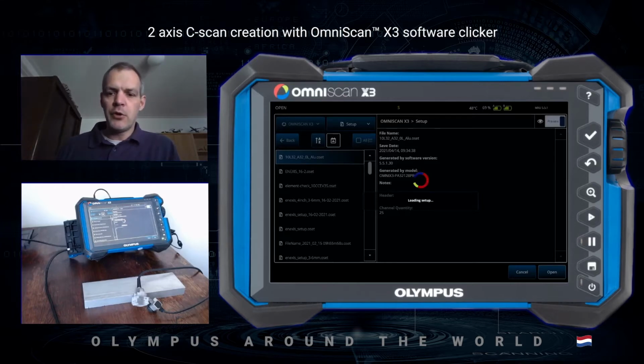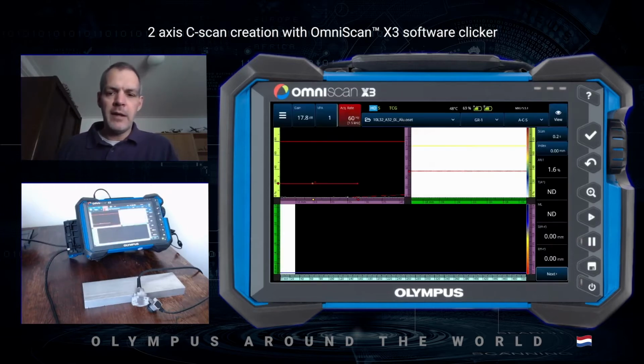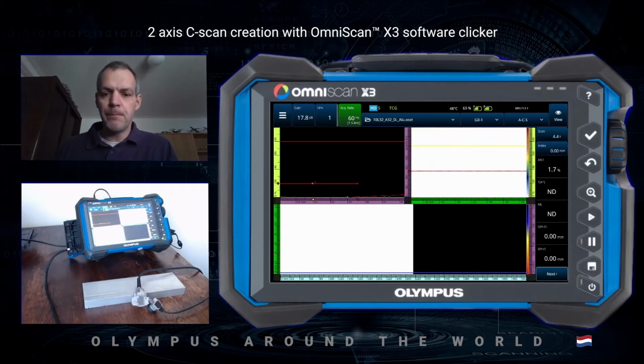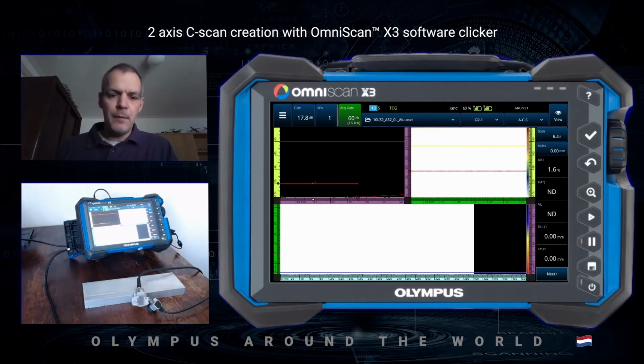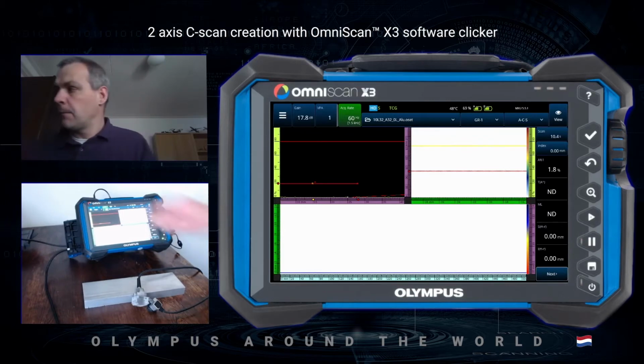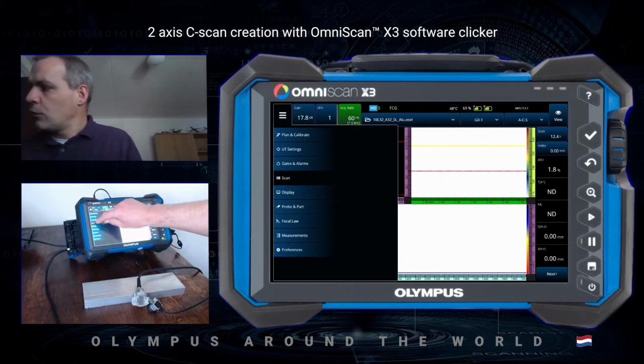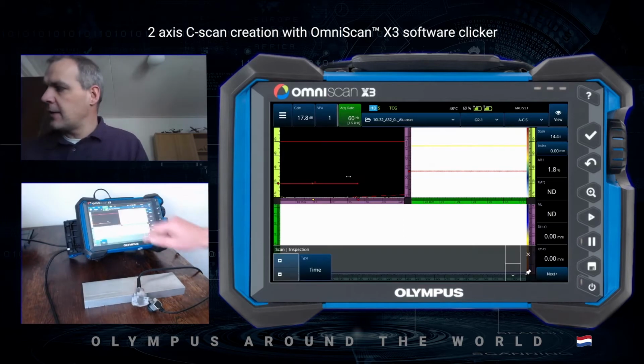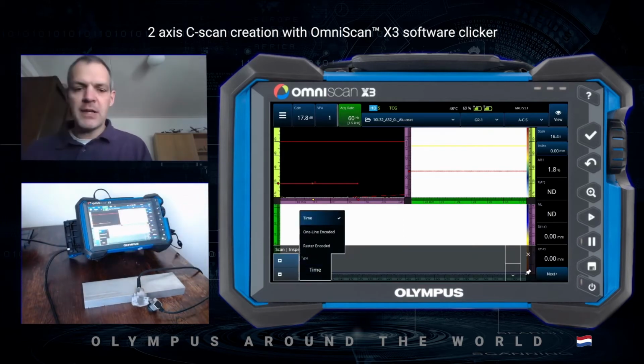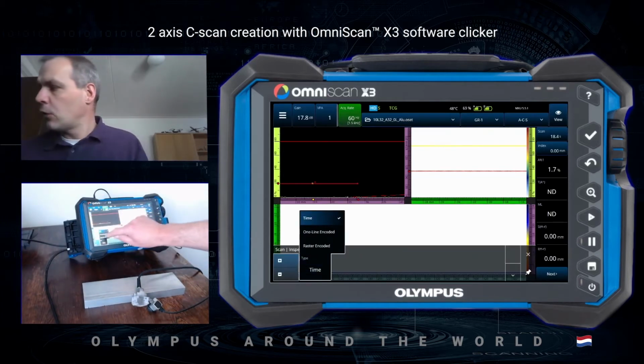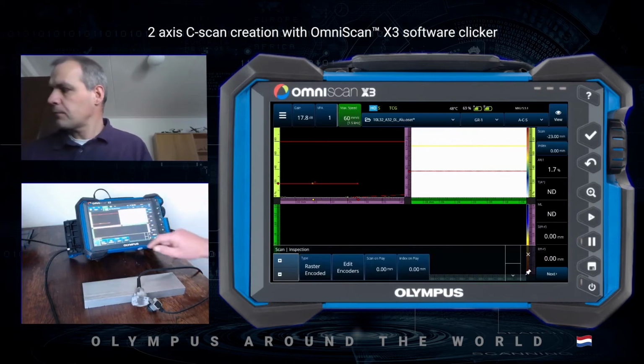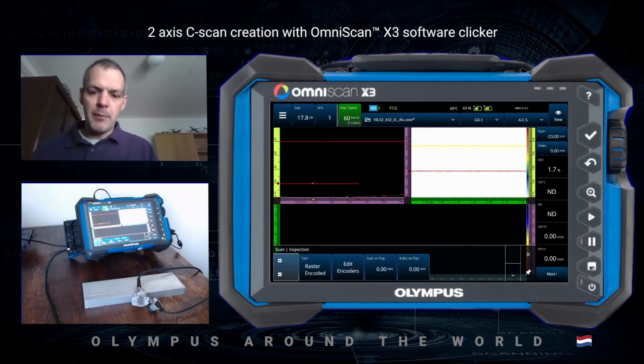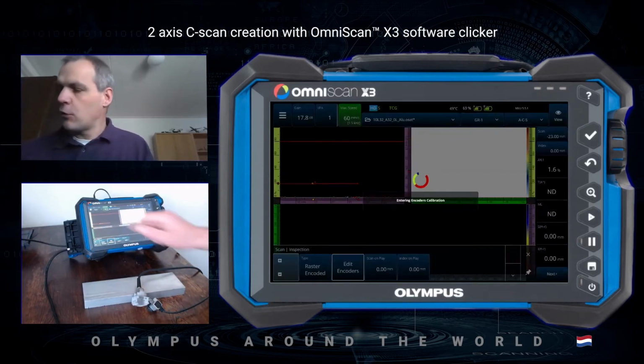I also adjusted some views, so when recalling the file, the A, C and S scan automatically appear in my screen. Next step is that I have to tell the instrument that I want to make a raster scan. Go to the scan menu, select inspection and change the inspection type from time to raster encoded. Some additional buttons appear.